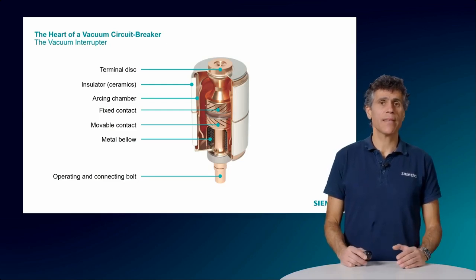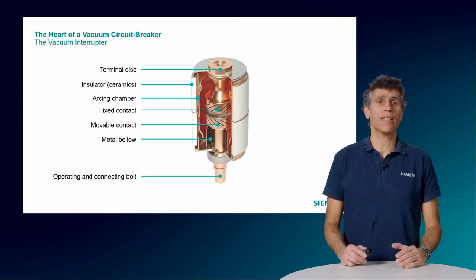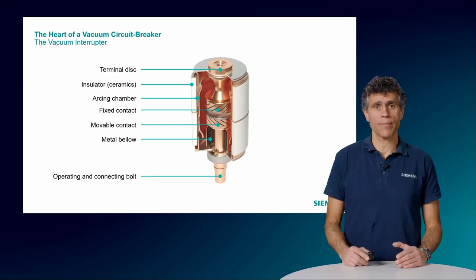The terminal disc is a metal plate or disc that is connected to the external electrical circuit. It acts as the entry and exit point for the electric current within the vacuum tube. Terminal discs conduct the high currents and are connected to the fixed or movable contacts inside the breaker. The insulator is typically made of ceramics. It supports the whole vacuum tube and electrically isolates the internal parts of the vacuum tube from each other and from the external casing. They prevent current from leaking through anything other than the designated path between the contacts.